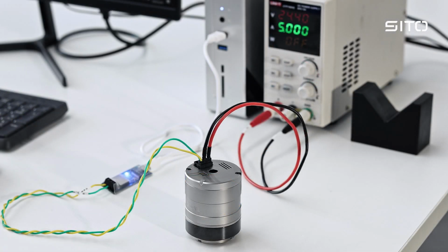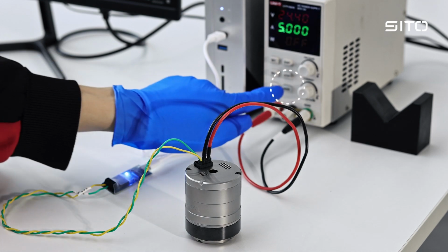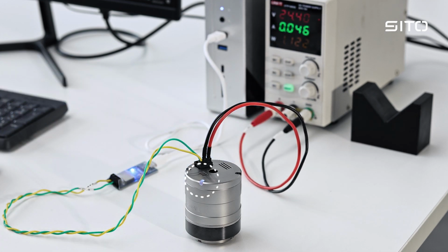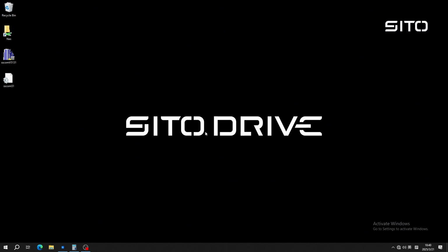When powering on without any operation, first observe the current of the power supply, which should be 50 mA plus or minus 10 mA. If the current is abnormal, immediately turn off the power. The indicator light of the actuator should be blue. After confirming that there are no abnormalities, we will proceed to the upper computer software of the TA actuator.